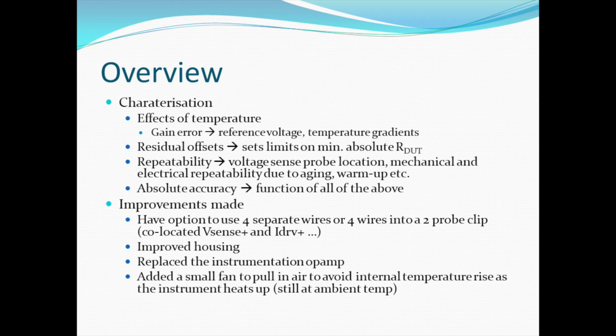The third thing is the repeatability, which is also kind of important when you do very low valued resistances where probe positioning makes a difference, mechanical and electrical related effects, perhaps due to the dissimilar metals or various contact related stuff, again for low resistance makes a difference. And there's also the effect of aging of components, warm up time where your meter may be warming up or your instrument itself is warming up. So all these have to be taken into account when you're doing kind of precision measurements in these very low value resistance cases. And of course, absolute accuracy is related to all of the above three things I just mentioned. So we will look at that and compare with a standard resistor in terms of characterization.